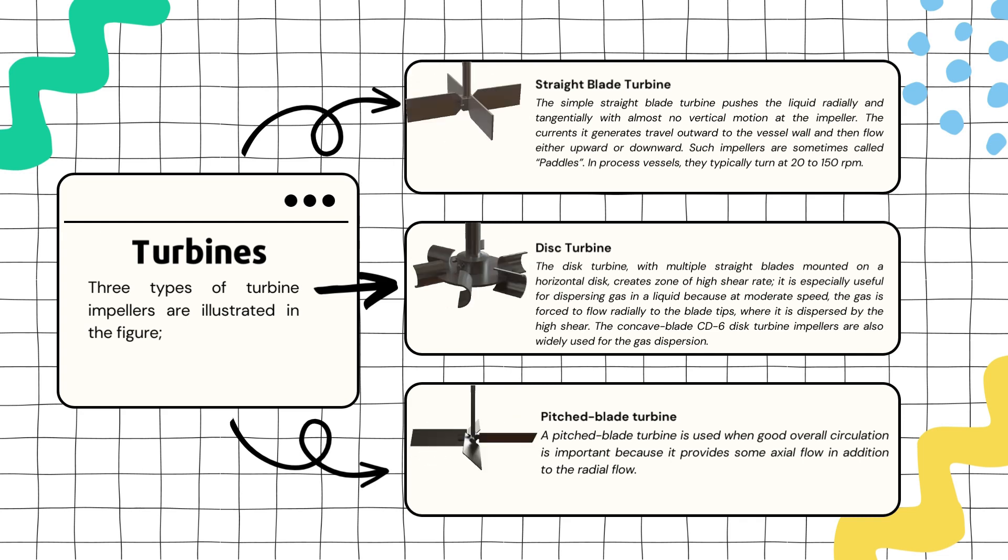This type of impeller has straight blades and mainly pushes the liquid outwards in a radial and tangential direction without much vertical movement. The currents it creates move towards the wall of the container and can then flow either upward or downward. Think of it like a paddle wheel turning slowly in a process vessel, typically at speeds ranging from 20 to 150 RPM.